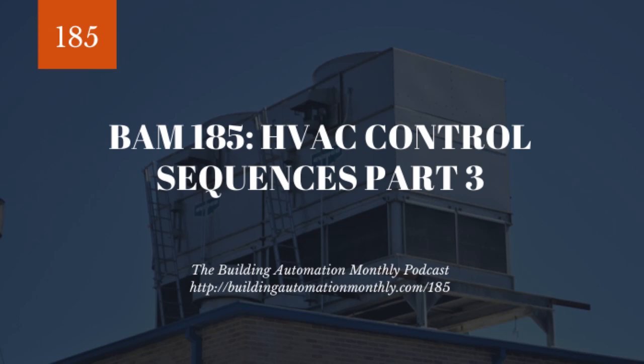And like I said, we'll talk about those sequences in a second. We also typically will have cooling valves, and we'll typically have low limit sequencing, and we'll talk about that in a second. And finally, we will have outdoor air dampers and return air dampers as well, typically controlling the economizer as well as potentially CO2, and controlling the CO2 either via a CO2 sensor or controlling it via just using our ASHRAE 62.1 settings, which once again, we're going to talk about in just a second.